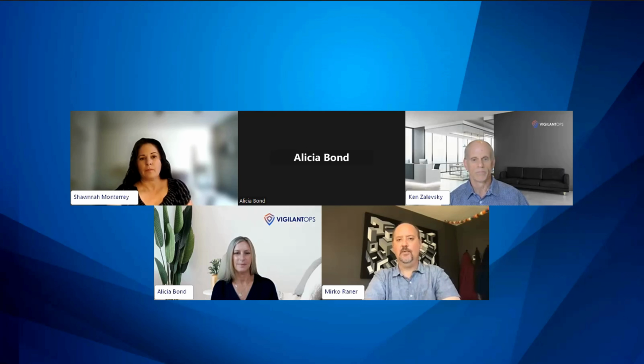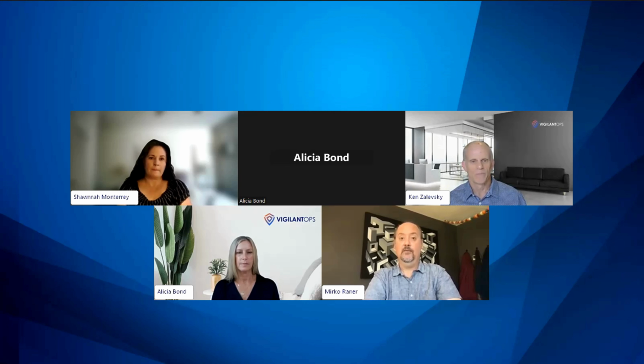Yeah, I can share some best practices definitely, and strategies for preparing the cybersecurity part of your submission, so that hopefully it won't come back with deficiencies. So the one thing I want to reiterate, one of the biggest mistakes I've seen at the FDA is that companies assume their device is not a cyber device, and they will just not submit any cybersecurity documentation, or a single page that says not applicable. So make really sure. It's possible that your device is not a cyber device, but in this day and age, if it's a software-based device, it's very unlikely.